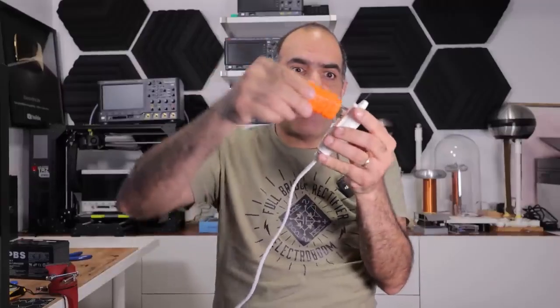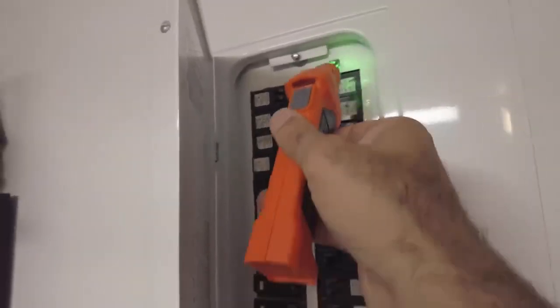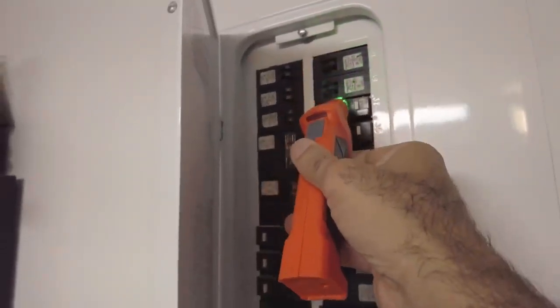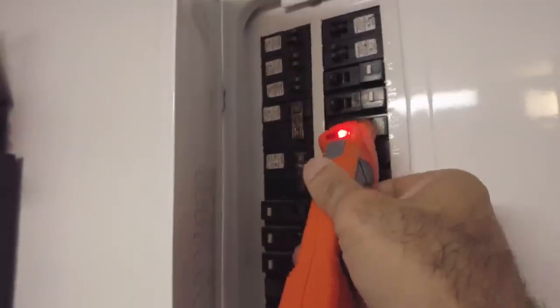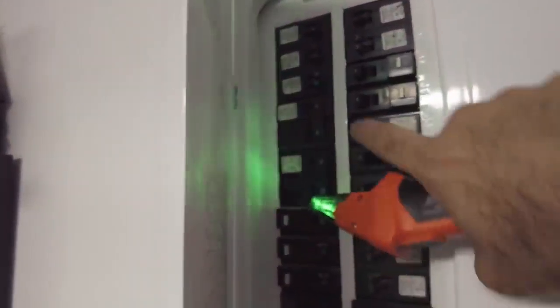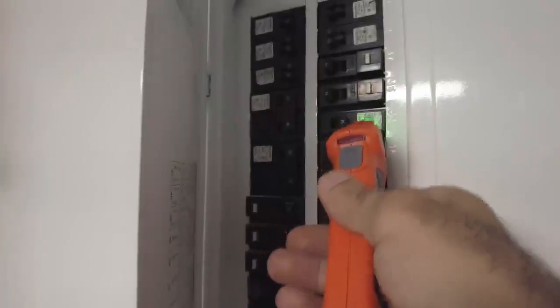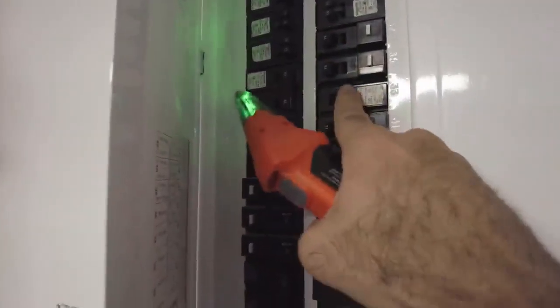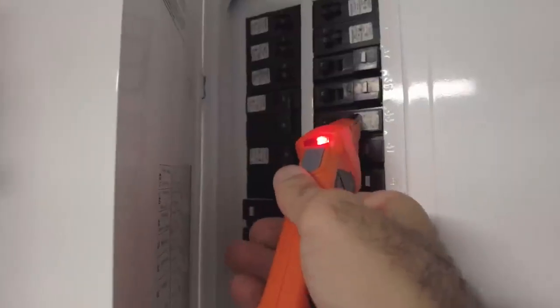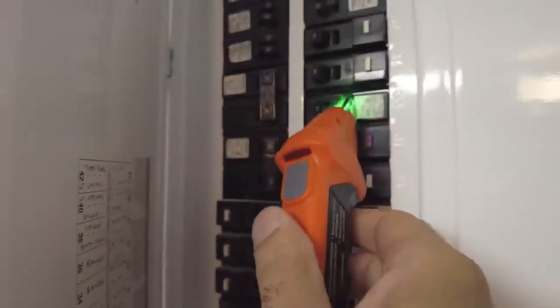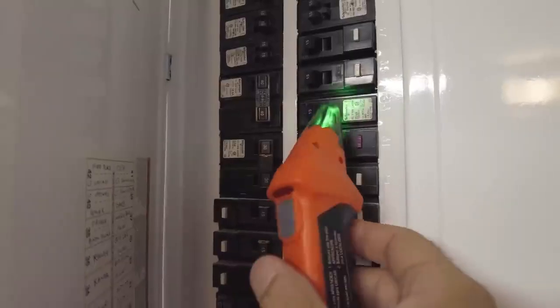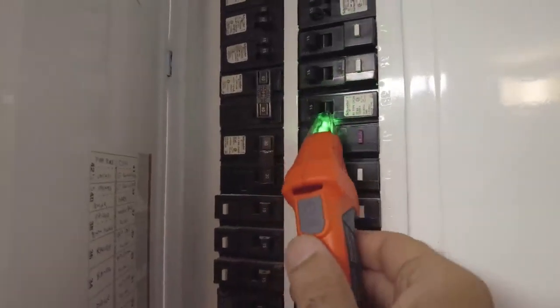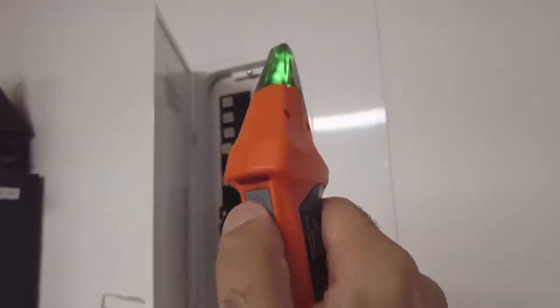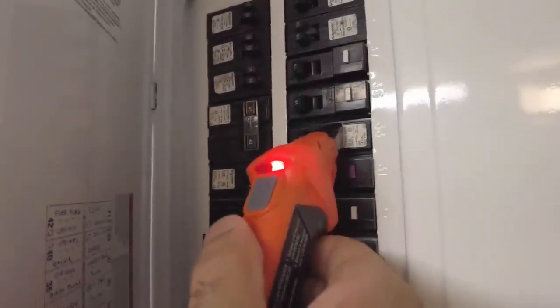So you plug this into the outlet you want to find the circuit breaker for, to inject the magic signal into it. On this side, the device has a sensor you can scan the breakers with. It sounds like a metal detector. Oh, there you go, it finds the right breaker. If I turn it off, the signal goes away too, and if I turn it back on, there you go. It seems like the sensor doesn't sense well after some use, due to some active gain adjustment I assume, so you move it away from the signal, press the reset button, and it starts sensing again.